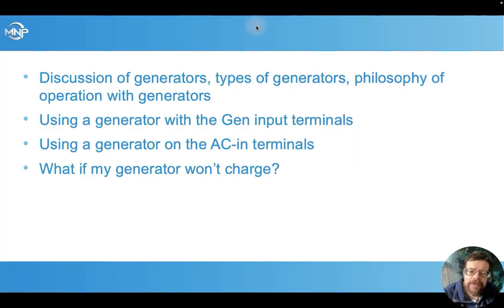We're going to talk a bit about generators in general for off-grid systems, types of generators, and the general philosophy of using generators for backup on off-grid solar power. Then we'll go into some of the details of using a generator with the MidNite all-in-one inverter, using it on the gen input terminals or the AC in terminals, and go through the programming in the app of how you set up the generator. And then we'll talk a little bit about some of the common causes, and what to do if your generator won't charge the batteries. It's running, but it won't charge.